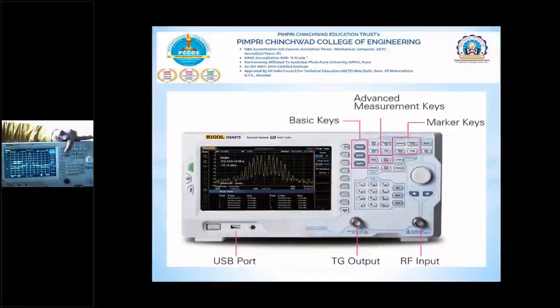Okay, once we press span, a window appears, and by default it shows 100 kilohertz. But our span is only 2 kilohertz. So we have to reduce that 100 kilohertz span to between 2 and 10 kilohertz, so that we can analyze that particular frequency component, because the overall frequency component span is up to 2 kilohertz. There is one big knob here, you can see it on the PPT. Using this knob we can reduce the span. As you can see, the spectrum span is also reducing like this.